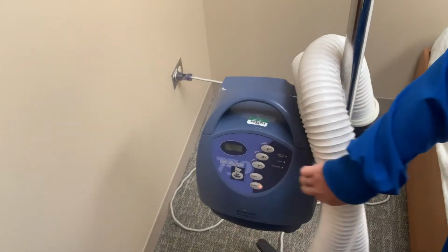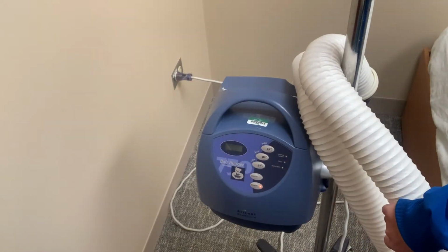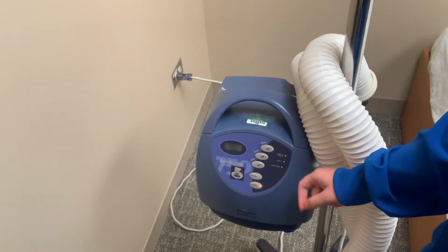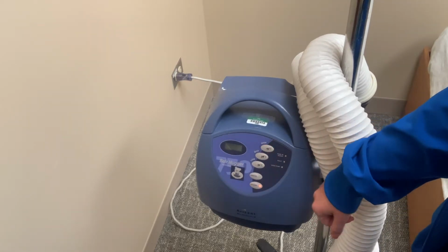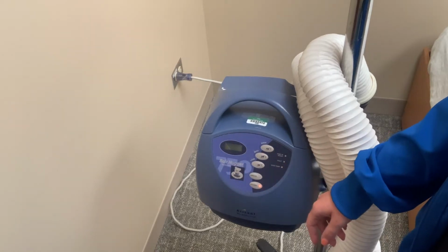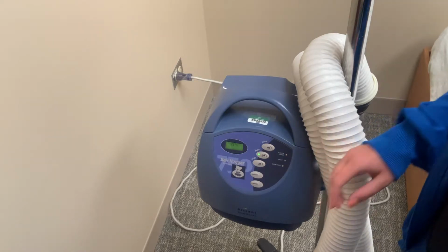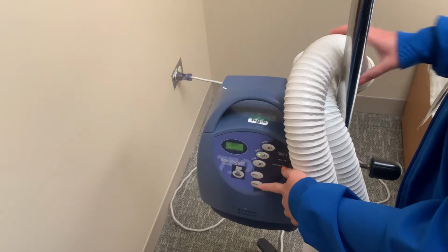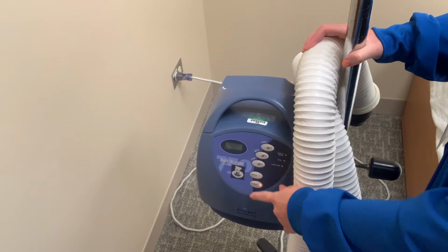All right, so setup of the Bair Hugger is actually very easy. All you do is plug it in and it turns on. There's no power button on it, which sometimes can confuse people. Plug it in and it'll turn on, and you have 3 temperature choices: low, medium, and high. Depending on how cold they are, decide which one you're going to go with, and all you do is click it and it turns on and starts blowing through here. And to turn it off, say you want to change the patient or something, just press standby.